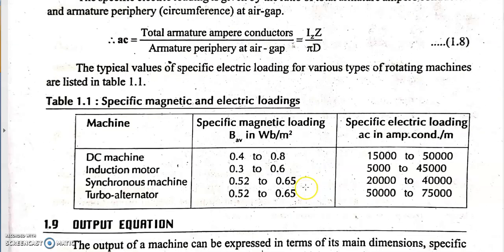The typical values for specific magnetic loading B_average range from 0.4 to 0.8 webers per meter square, and for specific electric loading AC the range is 15,000 to 50,000 ampere conductors per meter.